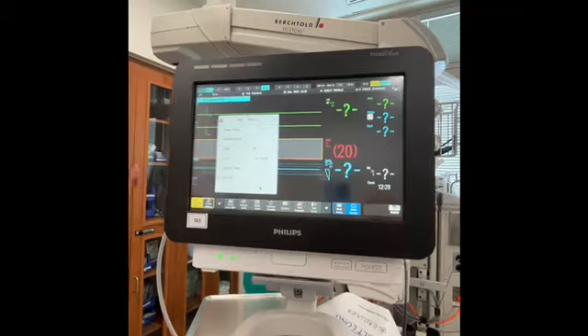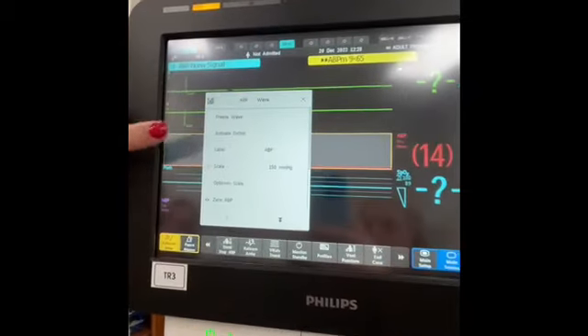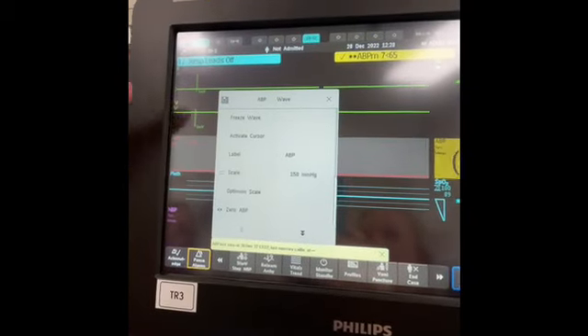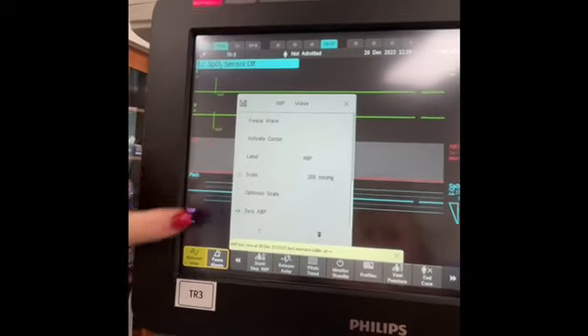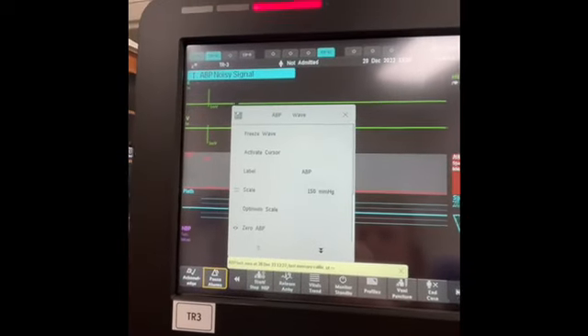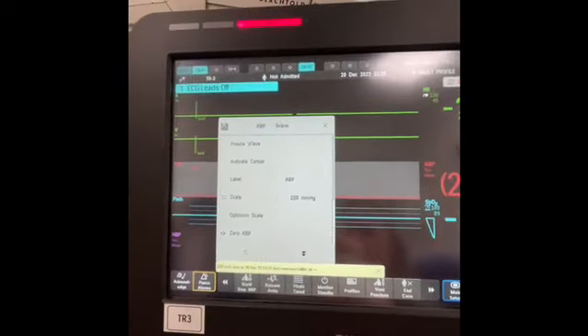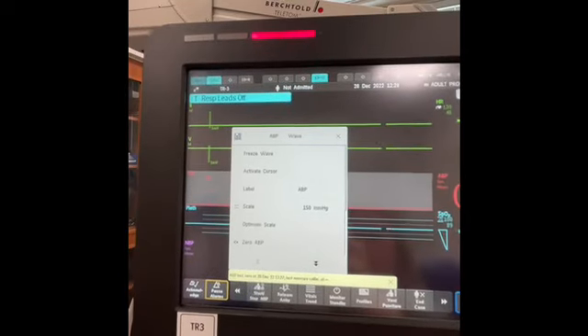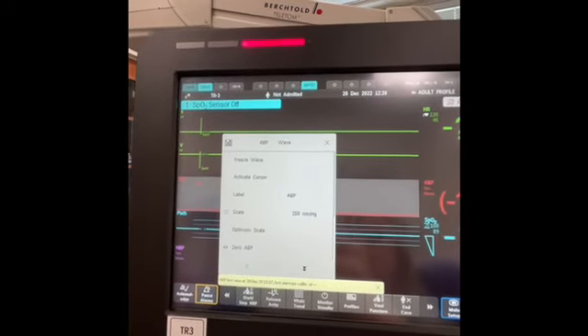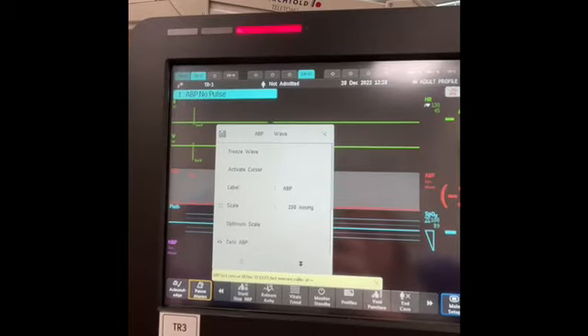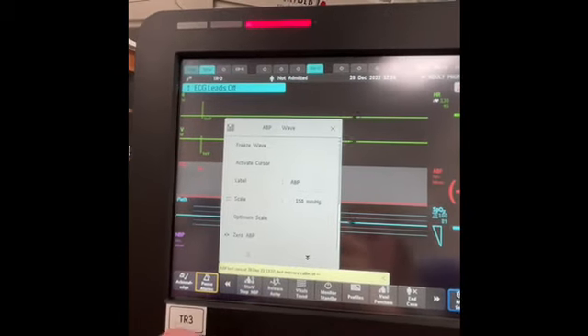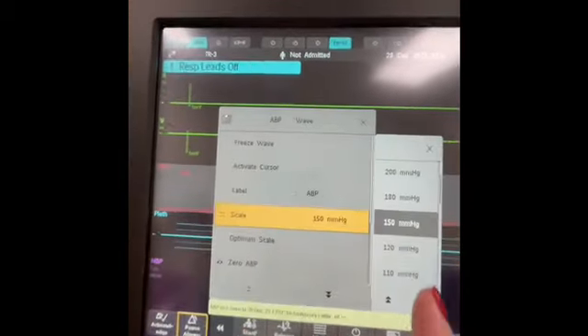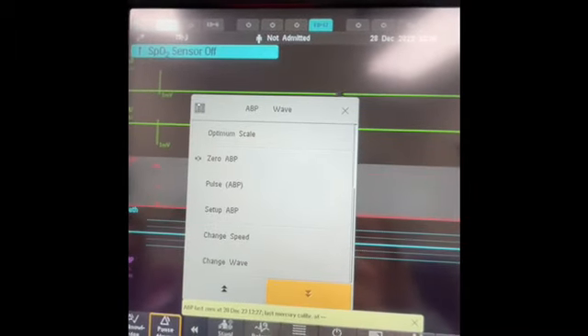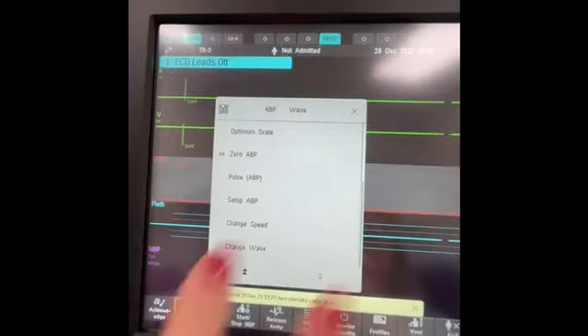If you push the monitor here, you can change the scale. If your art line isn't getting a very good reading, maybe it's over dampened or flat, and you've checked all the things: the line is not kinked, your bag is pressurized, it's attached to the patient. Sometimes you need to adjust the scale. So you can click on scale and adjust the actual size of the waveform itself. It's not connected to a patient, so we can't really see that.